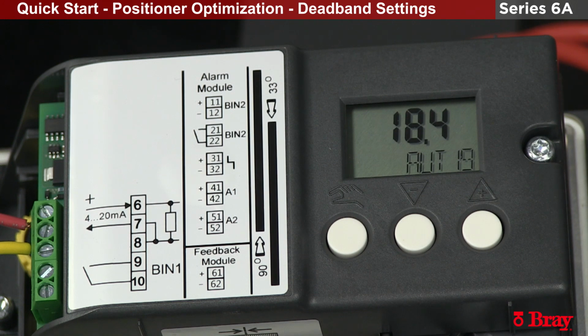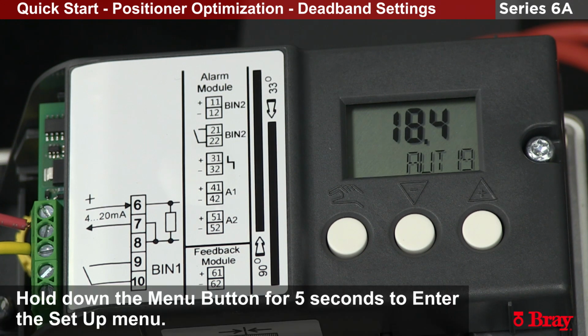In cases with butterfly valves, the positioner doesn't need to do any controlling in the absolute closed position and the absolute open position. For example, travel from 1 to 3 degrees on a resilient-seated butterfly valve, no throttling is needed there. We can instruct the 6A to ignore loop power information for those fluctuations. So 4.1, 4.3 milliamps will be ignored, and the actuator will go full close. To do this, we'll go into the limits travel settings.